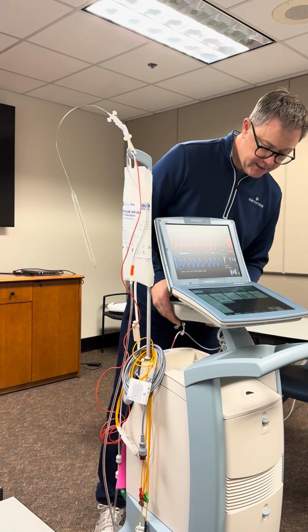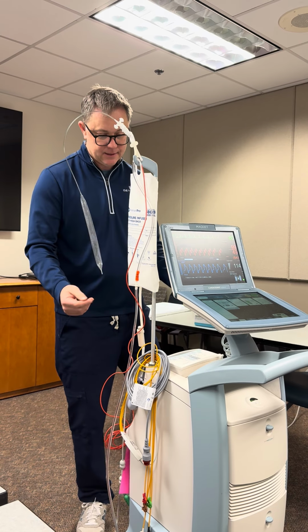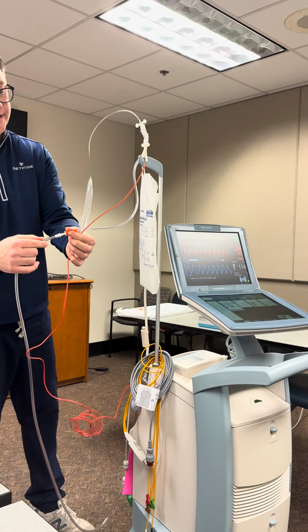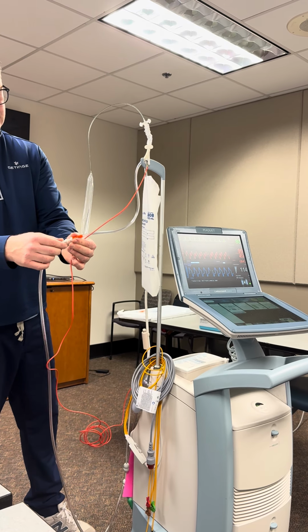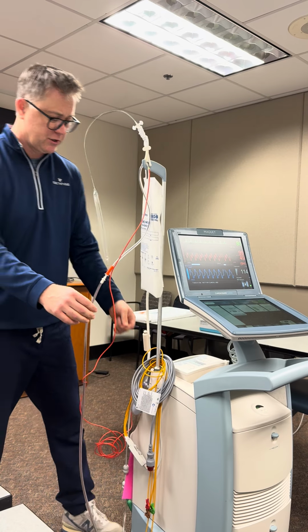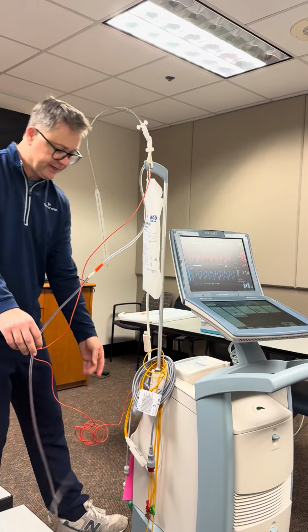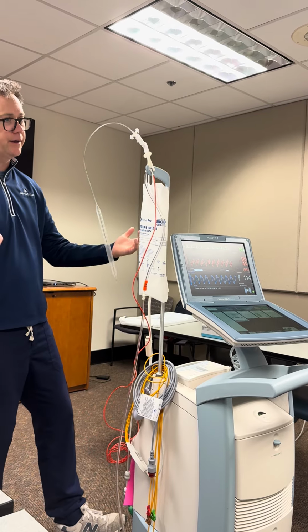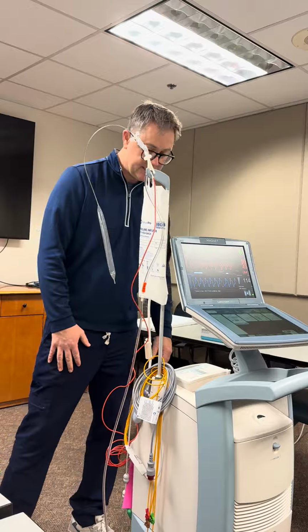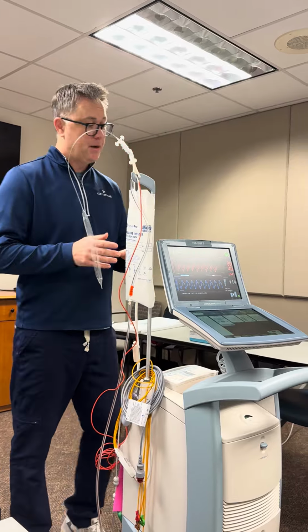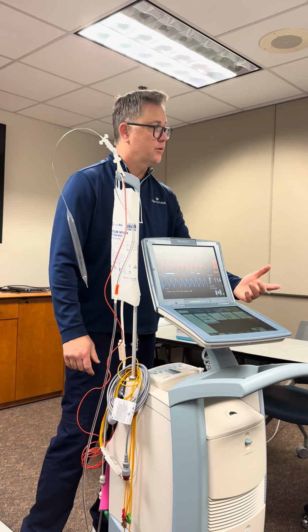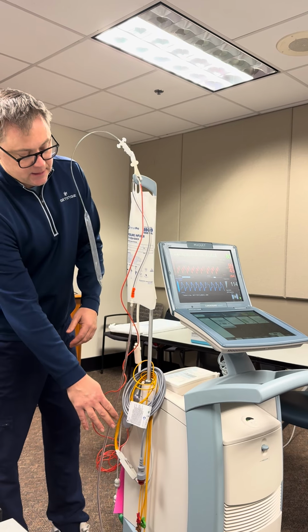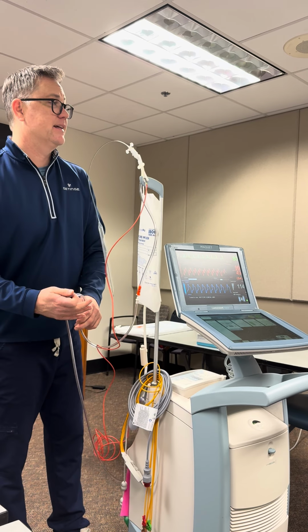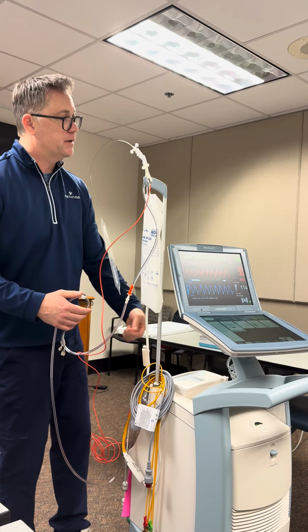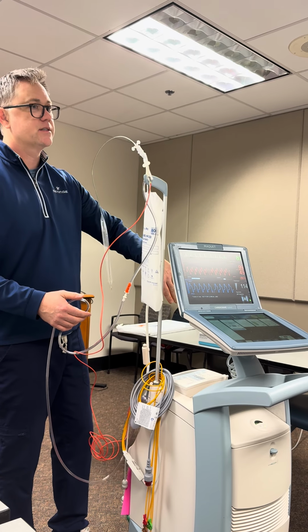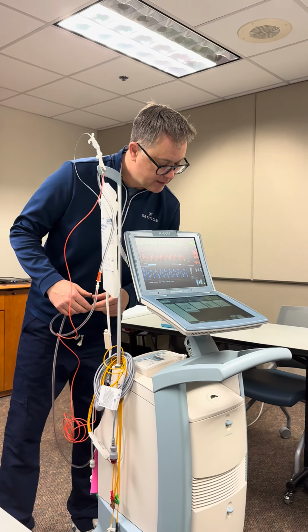Other alarms that you're going to see: disconnect. I didn't really talk about this. We've got two of these quick connects on here, so these can come undone fairly easily. They're just pressure locks, designed so that if one catches on a wheel or a bed rail it pops out real quickly. So just be aware they can come undone fairly easily. It'll stop the pump. You're going to have to reconnect it and hit start when that happens. And wait. It takes time because it has to do that whole startup again, since we've lost some helium. It's got to flush the rest of it and start up again.